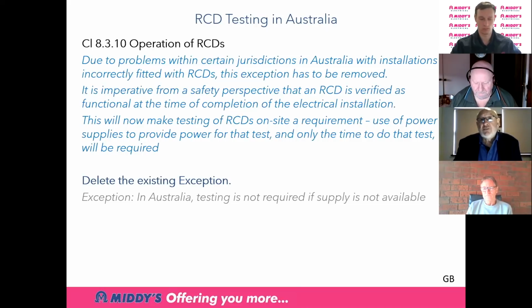From a safety perspective, it's imperative that you test on an installation that the RCDs operate correctly and do what they're supposed to do, which is to isolate your supply in the case of a fault. So this will now make testing of RCDs on site a requirement. Now, this could be some of an issue in certain states, but I know in most states that I've heard, electricians are carrying around an inverter or even a gen set to provide power just while they do that test for the RCD. So it actually makes a lot of sense. If you're doing the job, you want to walk away, or you want your employee to walk away, from that job that they've just done and know that everything works well.